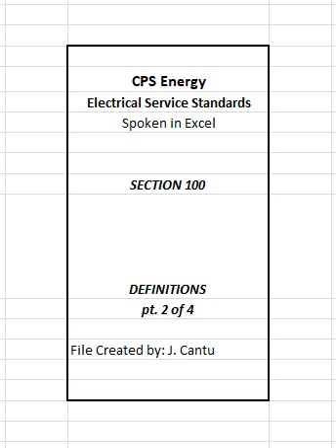A ground is a connection, either intentional or accidental, between an electrical circuit and the earth or some conducting body serving in place of the earth. Ground fault. An unintentional electrically conducting connection between an ungrounded, phase, conductor of an electrical circuit and the normally non-current carrying conductors, metallic enclosures, metallic raceways, metallic equipment, or earth.